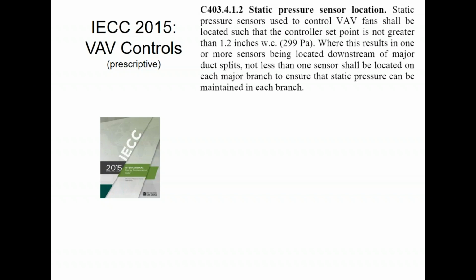Historically, on the VAV system, we have put the duct static pressure sensor 2/3 down the duct, just because we were told to do that. No real science behind it, just kind of a good average guess, right? An art, if you will. Ideally, we would have measured static pressure drop at every single VAV box and controlled the worst one, but no one's going to buy all those controls. So we put it 2/3 down the duct and called it a day.